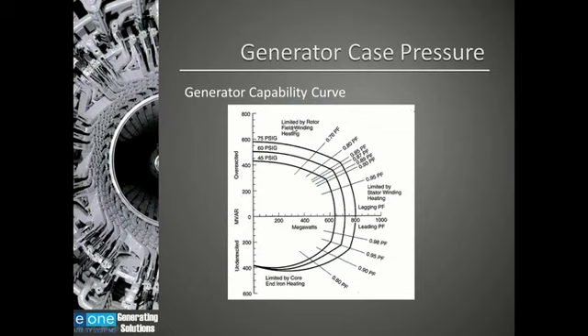I mentioned that it's critical to know what the generator case pressure is, and this generator capability curve indicates why it's important to know the generator case pressure. As you can see, the higher the pressure, the more megawatts that can be produced. A generator capability curve such as this is supplied with each generator by the OEM.